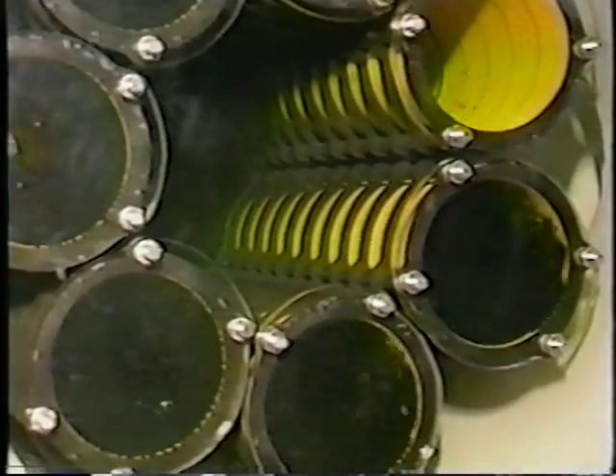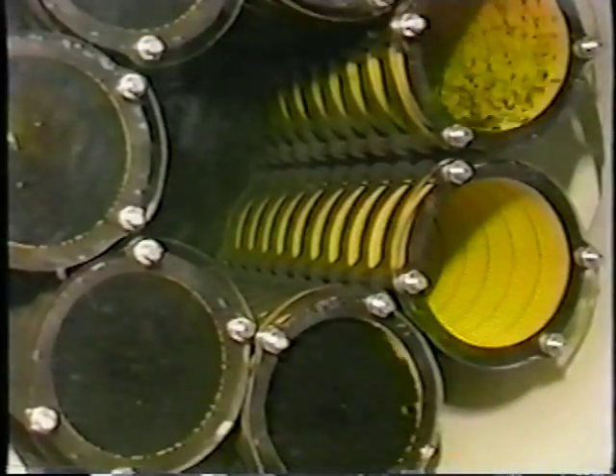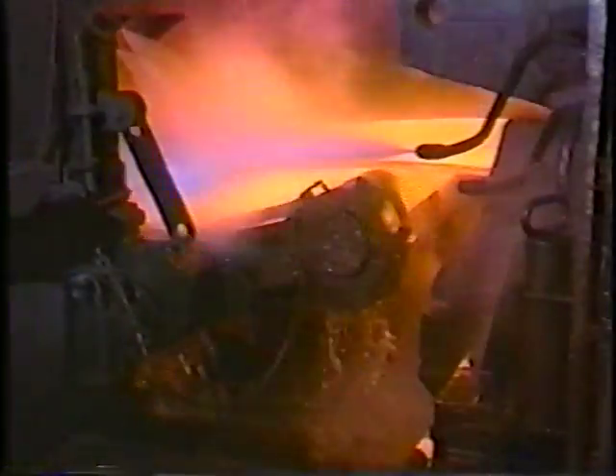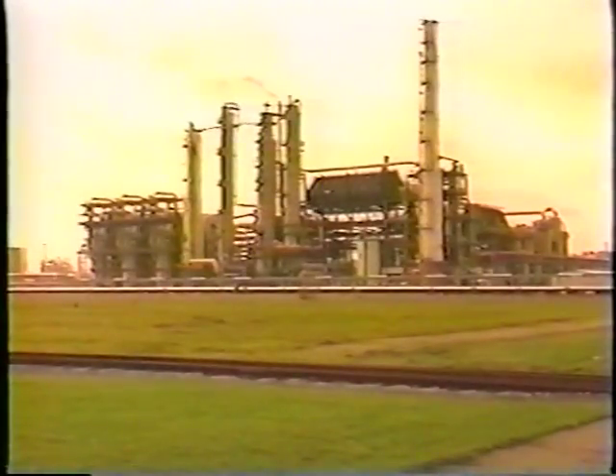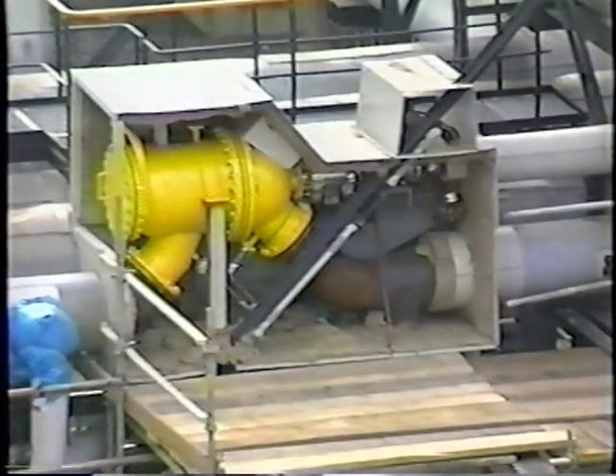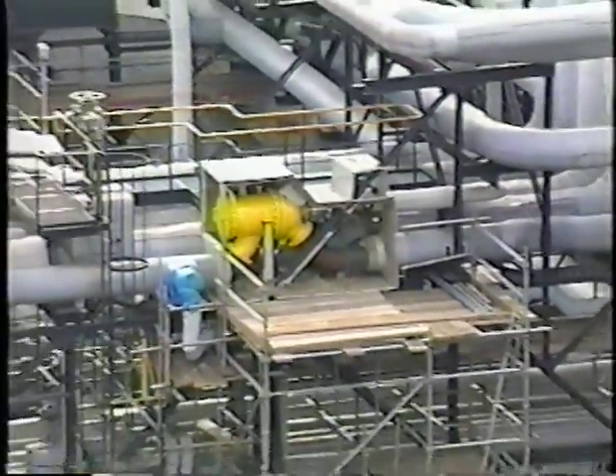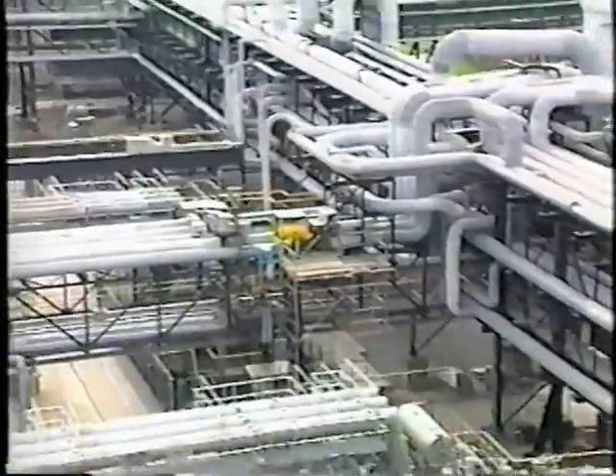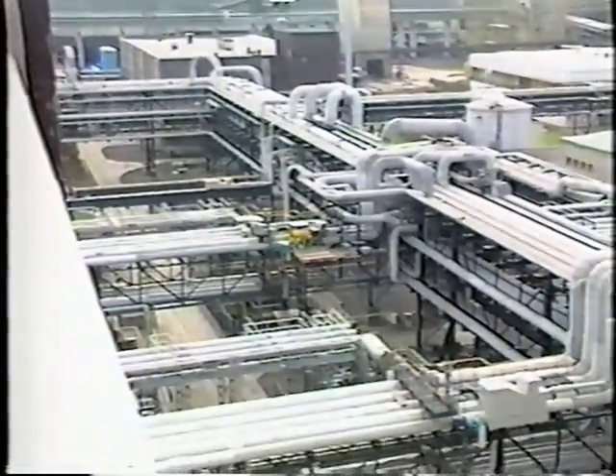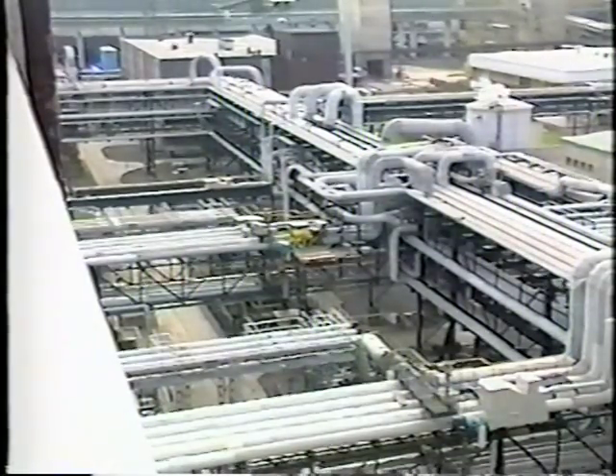Taprogge fine filters are used for purifying cooling and process water in auxiliary cleaning systems, in front of plate or tubular heat exchangers, in pump bearing, cooling and lubrication systems, for side stream filtration in cooling tower systems, for fire protection systems, and for treated spray water. This is the reason why Taprogge filtration systems are found in steelworks, chemical plants, and of course in power stations. At this power station, 3 Taprogge fine filters have been installed in the auxiliary cooling system. Fitted with filter cartridges with a gap width of 300 microns, they reliably filter algae and sludge from the cooling tower water supply. Plant availability has significantly increased following the installation of these Taprogge fine filters.